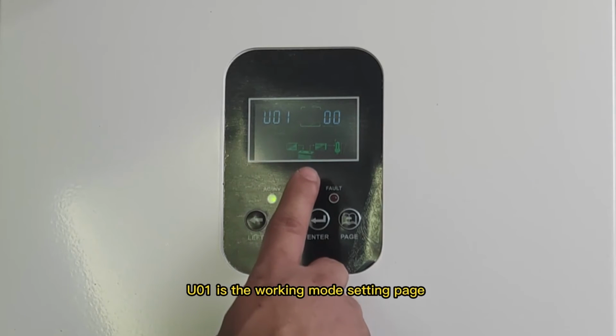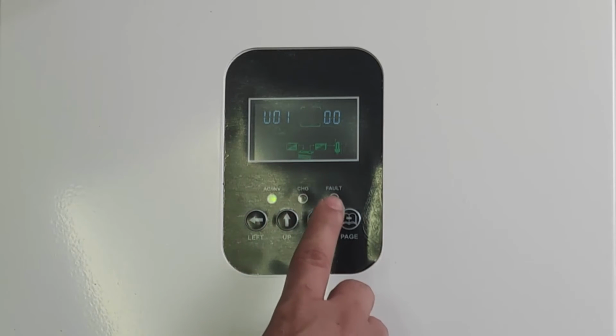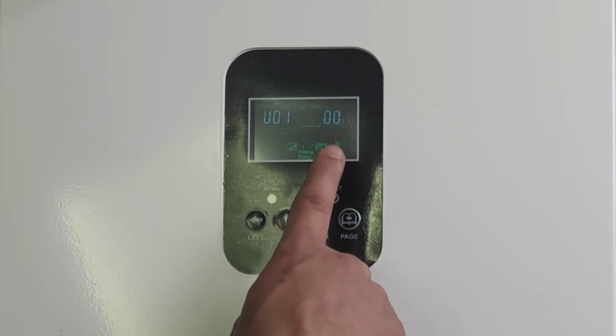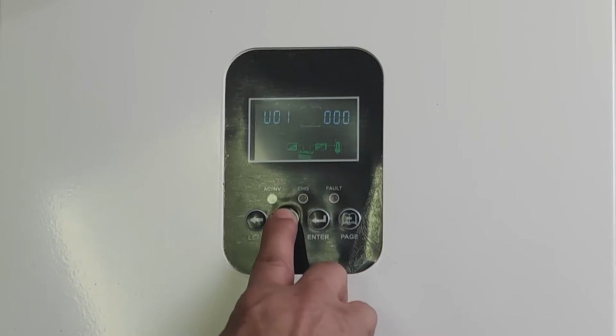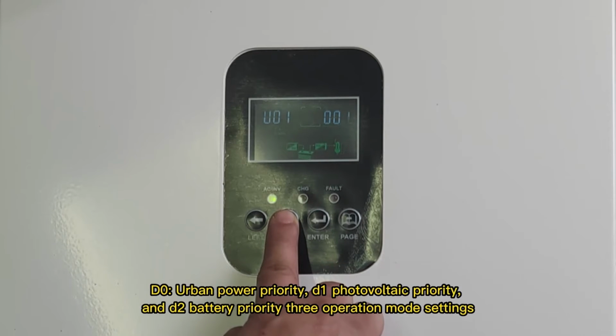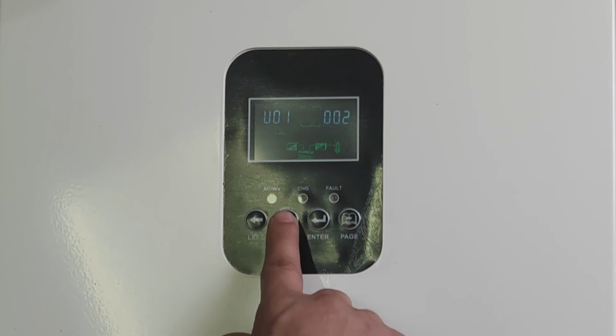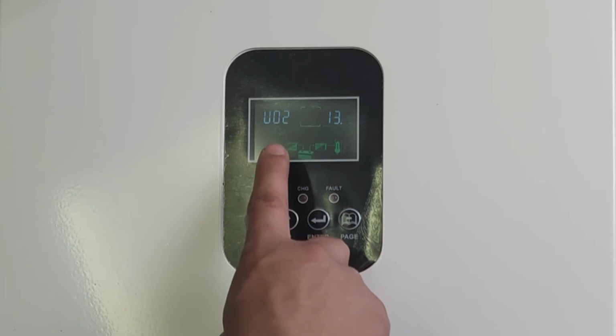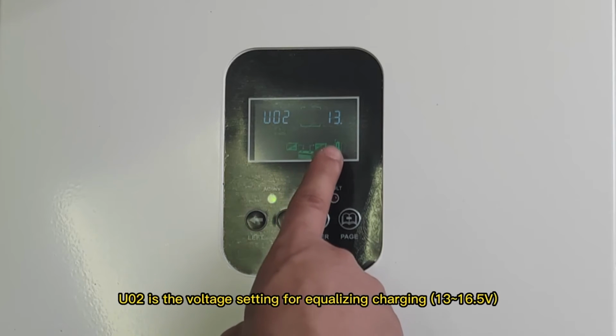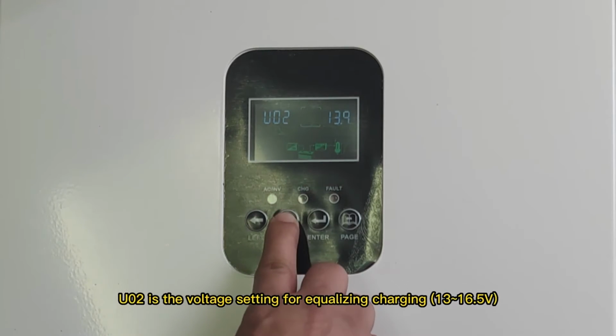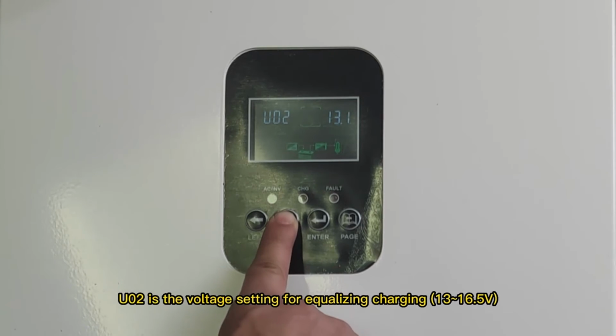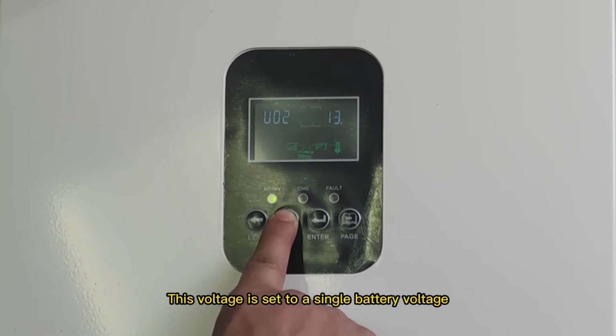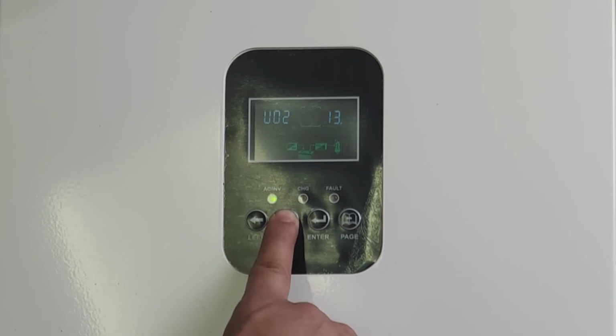U01 is the working mode setting page. D0, mains power priority; D1, photovoltaic priority; and D2, battery priority: three operation mode settings. U02 is the voltage setting for equalizing charging, 13 to 16.5 volts. This voltage is set to a single battery voltage.